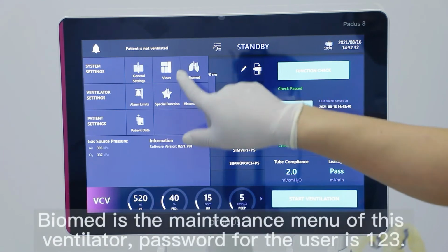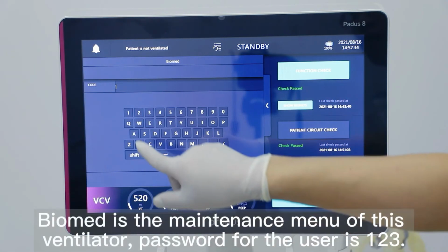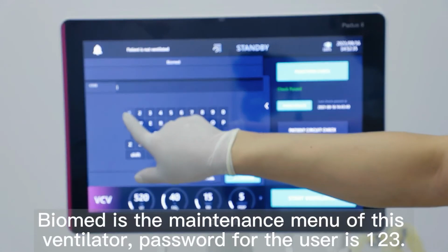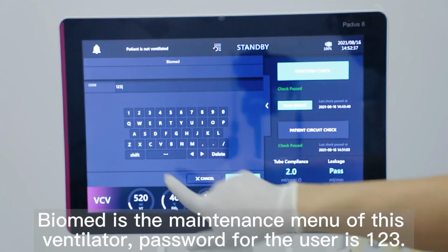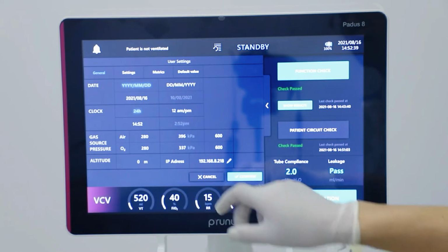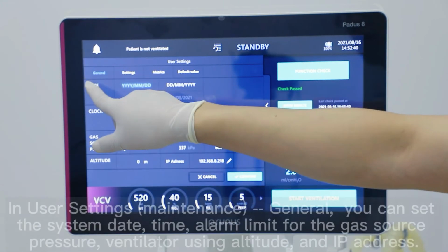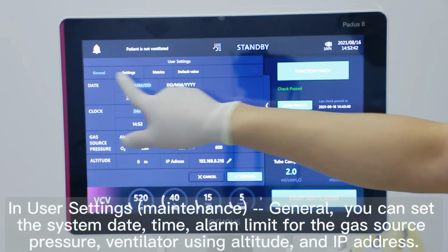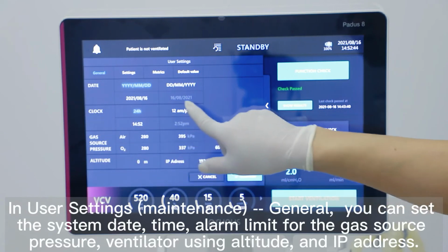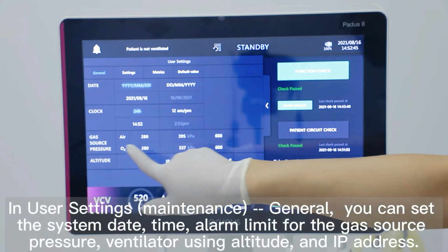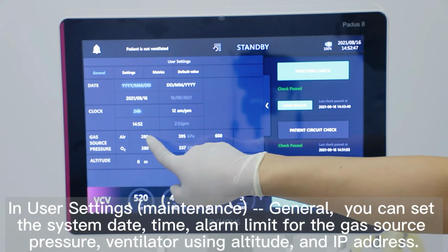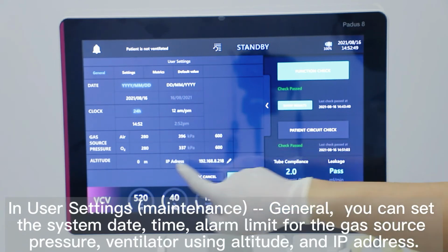Biomed is the maintenance menu of this ventilator. Password for the user is 123. In user settings, general, you can set the system date, time, alarm limit for the gas source pressure, ventilator using altitude, and IP address.